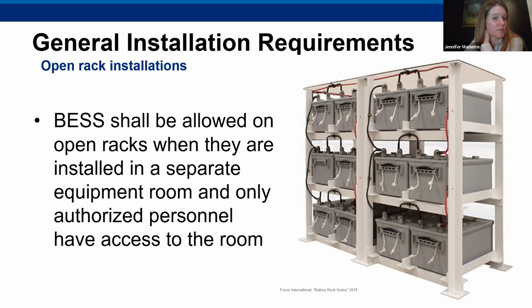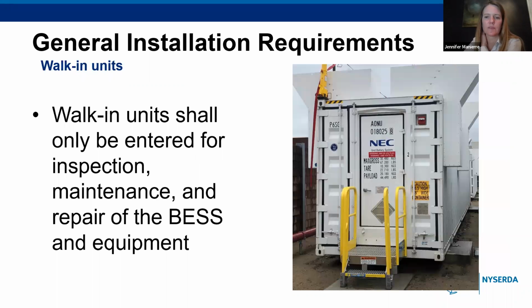You can choose to put energy storage systems on open racks, as long as those open racks here, not enclosed, are open for ease of operations and maintenance. You don't have to open doors to get to them. But if that's the case, they need to be in a separate equipment room that's locked off where only authorized personnel can have access. So walk-in units should only be entered for inspection, maintenance, and repair of the energy storage equipment. Otherwise, there should never be a human inside of them.